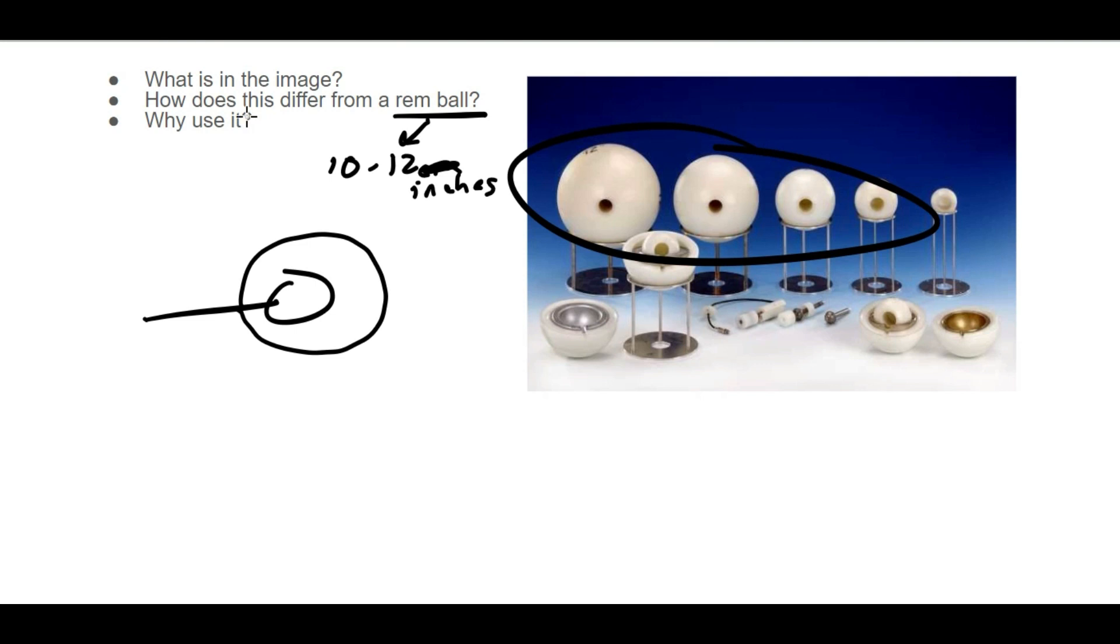Why use this? We use it for shielding when you have your door and potentially the ability for neutrons to be present during the beam. You want to verify that your shielding will be able to handle that. As a quick overview: a neutron comes in contact with the Bonner sphere, enters and is moderated to lower energies, the lithium iodide captures the neutron, then the gamma is produced and detected. The quantity we are measuring is neutron flux.